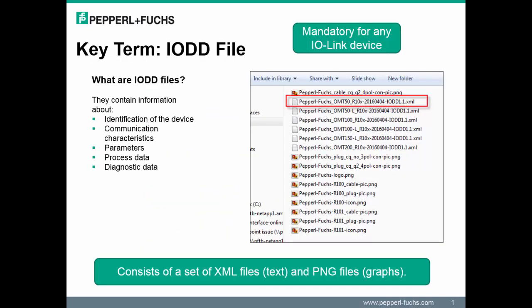Let's discuss the first key term we should all get familiar with relating to IO-Link: an IODD file. An IODD file — Input-Output Device Description — is mandatory for any IO-Link device. This file is needed to provide further details about the device, specifically identification, communication characteristics, parameters, process data, and diagnostic data.